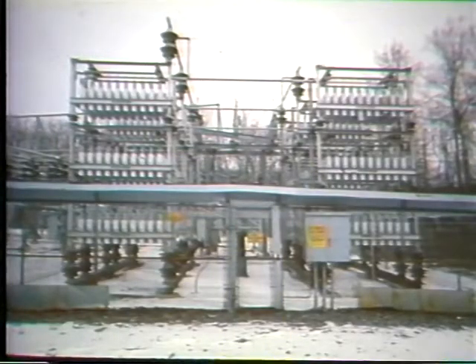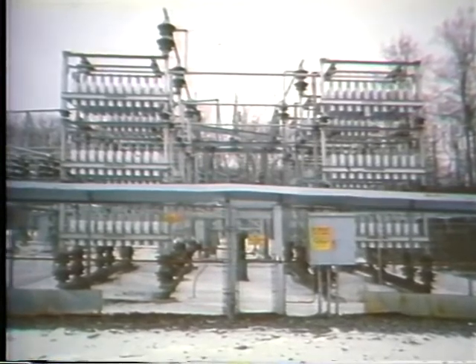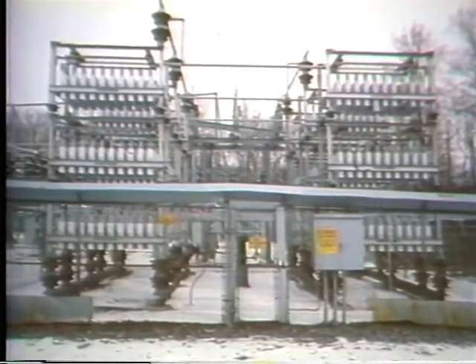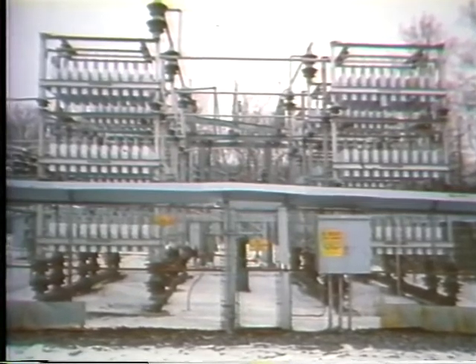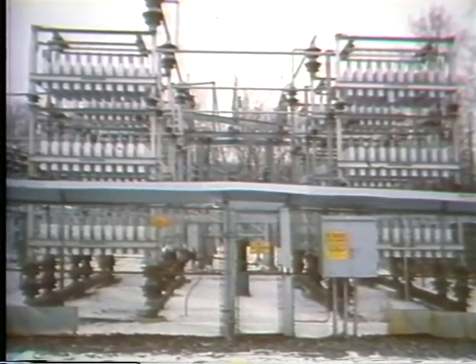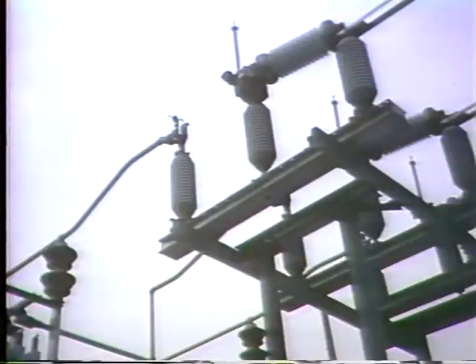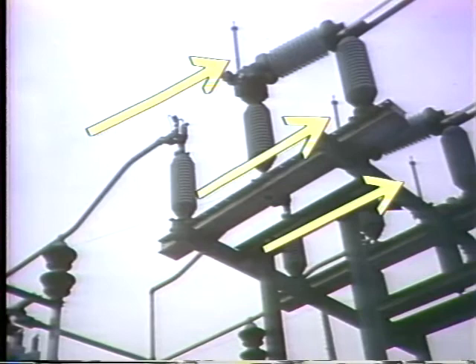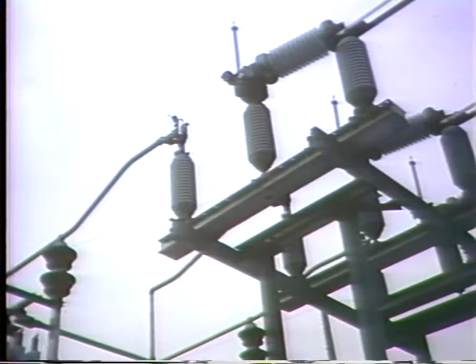A large capacitor bank can be even more dangerous. Hundreds of thousands of volts could be released here, so it's extremely important that they're discharged and grounded before any maintenance takes place. The first step is to de-energize the bank. This open disconnect switch means that the power's been cut. Now, internal resistors built into the capacitors will slowly discharge the bank for a period of at least 5 minutes, the minimum time for safe discharging.